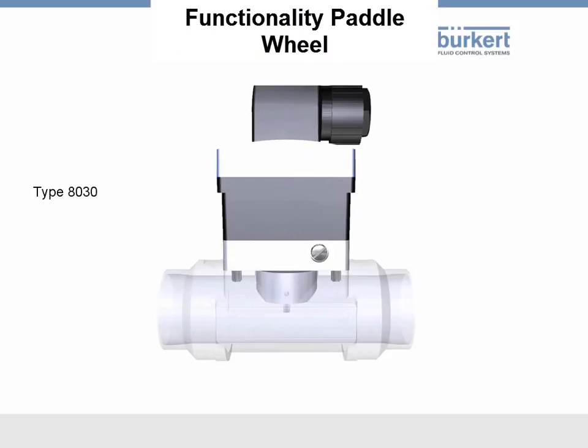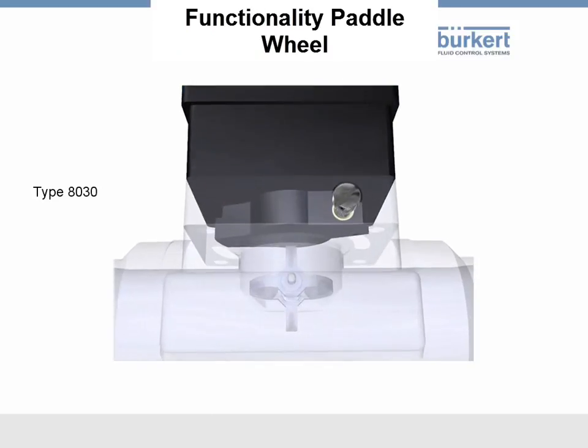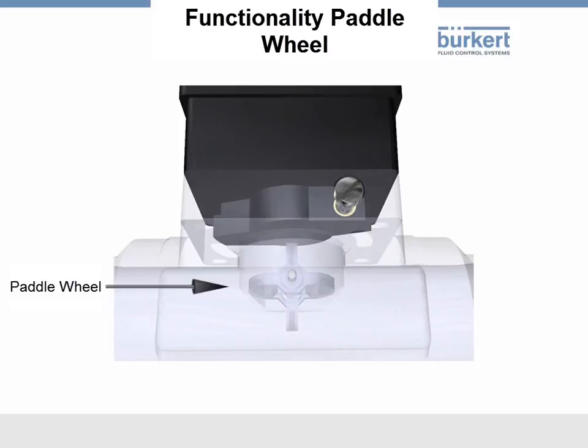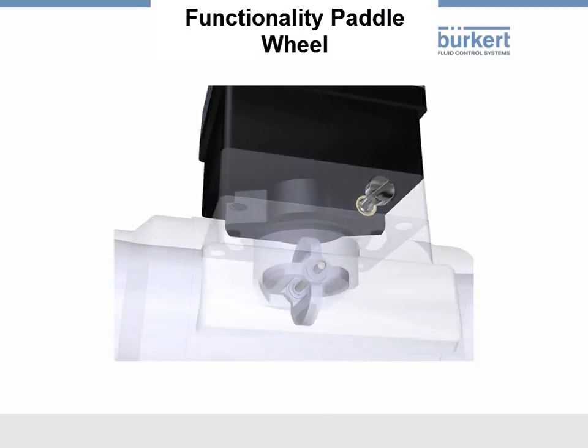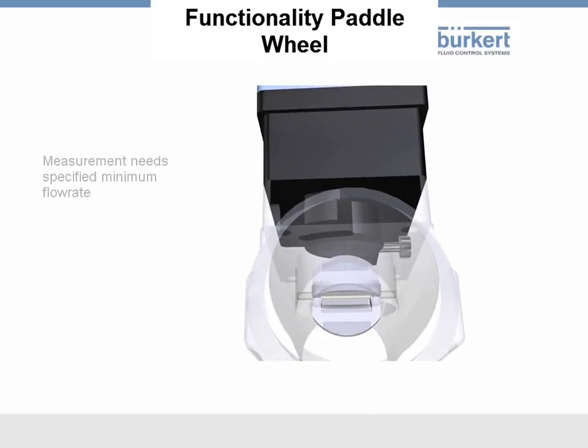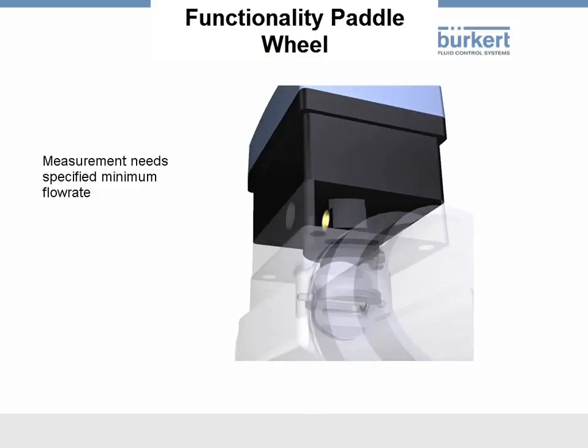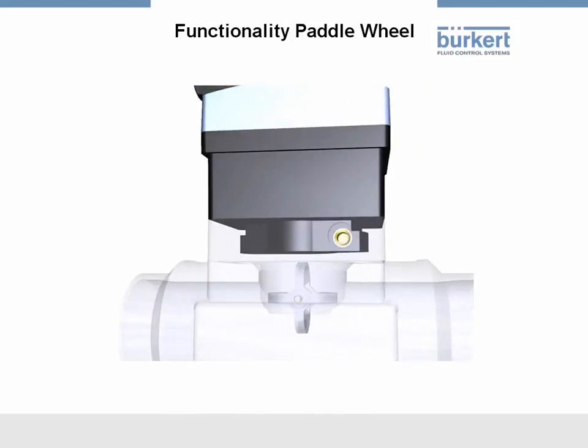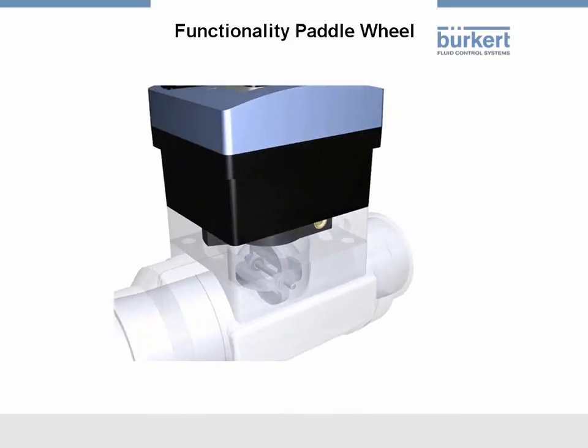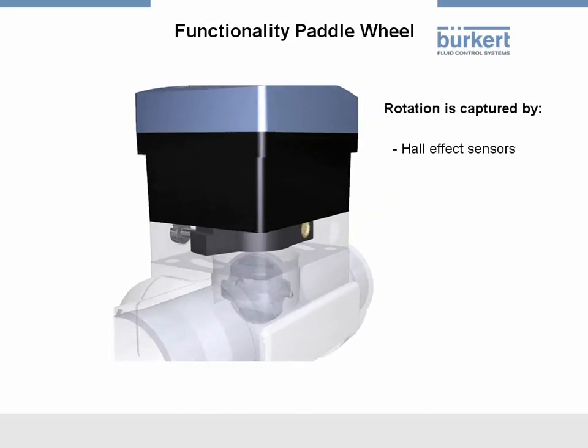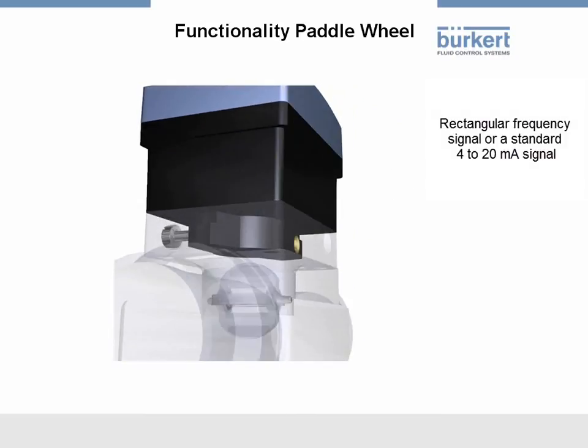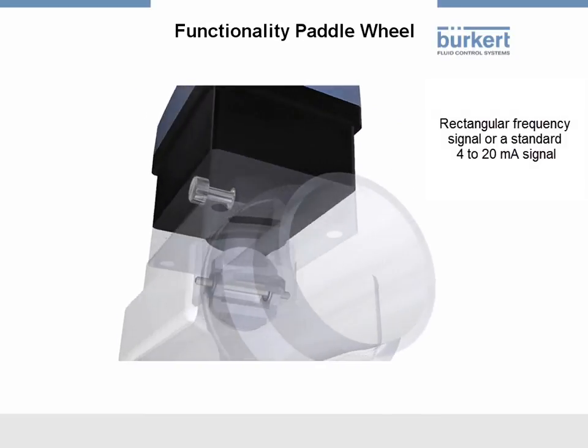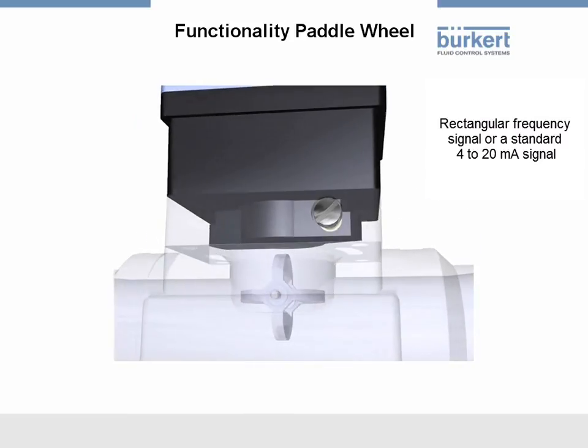You're probably curious about how paddle wheel sensors work. The paddle wheel is in a pipeline and is driven by a flowing medium. It's important to know that measurement is possible only above a specified minimum flow rate, since a certain force is needed to set the paddle wheel in motion. The paddle wheel rotation is captured by Hall effect, coil, or infrared sensors, and is converted by the electronics into a flow rate proportional rectangular frequency signal, or a standard 4 to 20 milliampere signal.